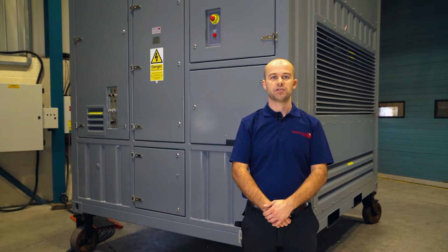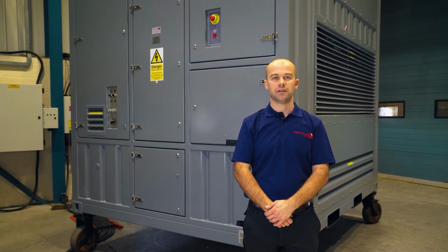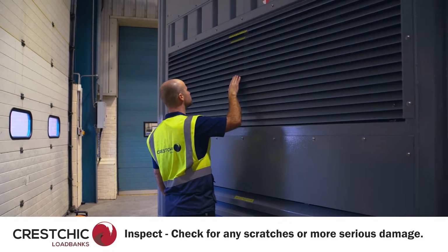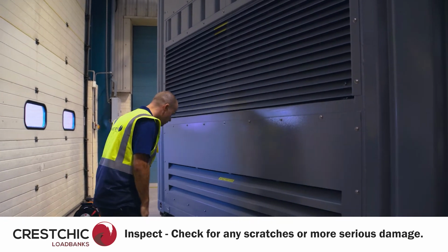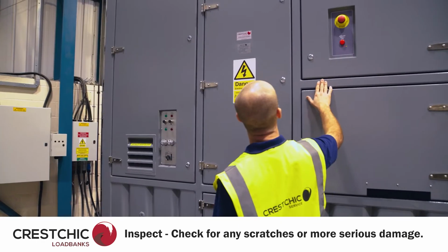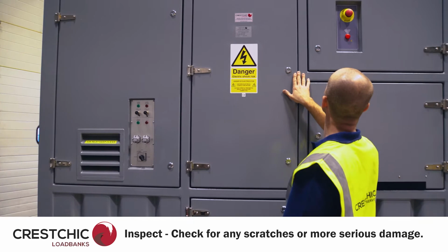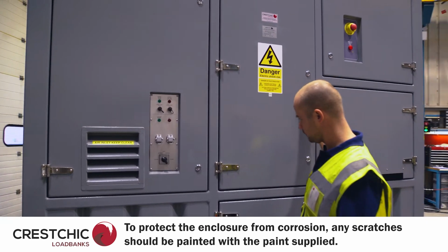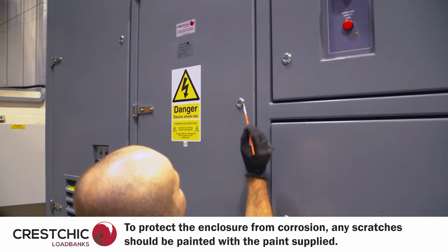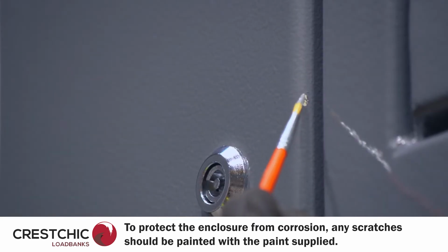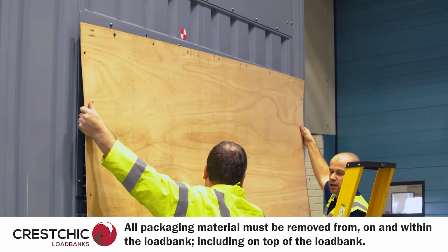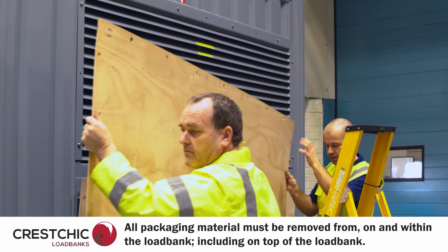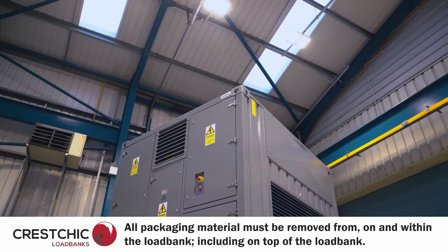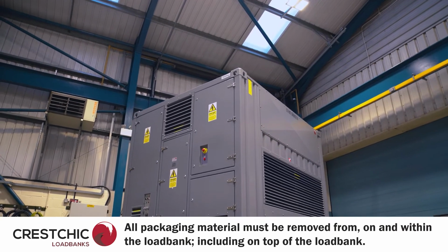The load bank has probably travelled a long distance from where it was manufactured. Therefore, the load bank should be inspected for any scratches or more serious damage that may have occurred during shipping. If there does happen to be any scratches, then this should be addressed as soon as possible to help protect the enclosure from corrosion. Before you can use your new load bank, the packaging material must be removed, remembering not to forget to check on top of the load bank.